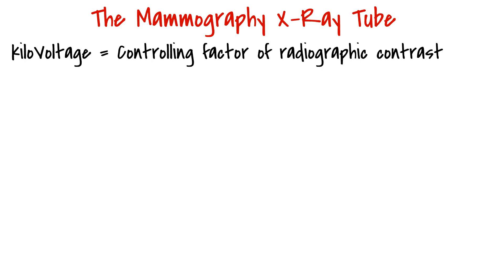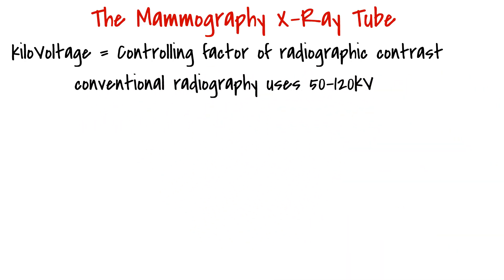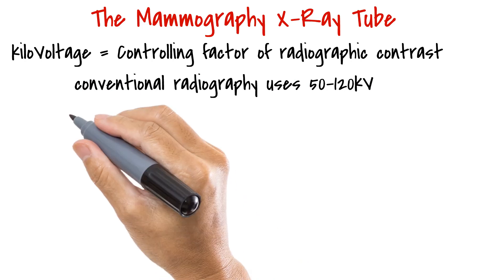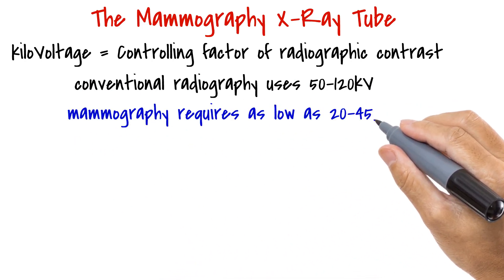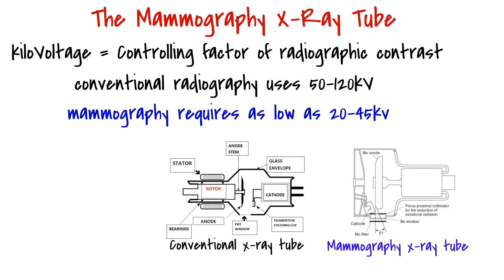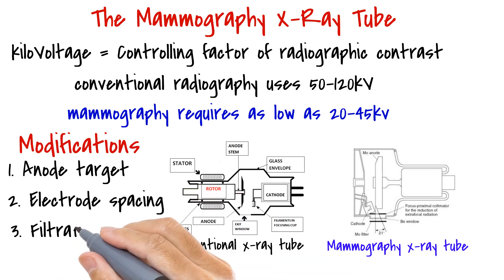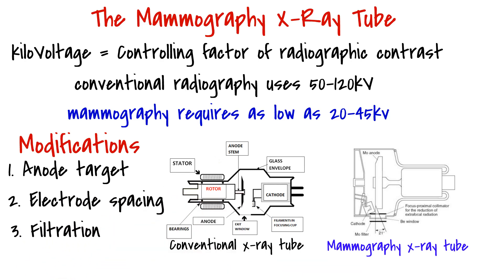Conventional radiography equipment produces X-ray beams of between 50 and 120 kilovolts. In mammography, we want the kilovoltage to be as low as 20 kilovolts. Conventional X-ray tubes are not designed to produce X-ray beams with kilovoltage this low. Thus, modifications are made to the conventional X-ray tube. These modifications are majorly seen in the anode target, electrode spacing, and filtration of the X-ray tube.